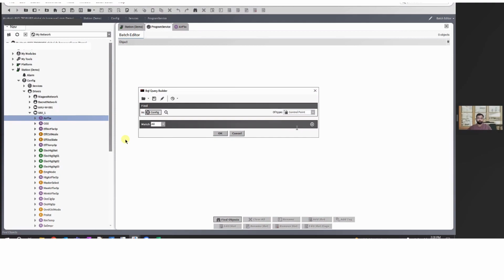In the find window, you can go to config since we're changing every point that has liters per second, to narrow it down to that. But what other options do we have? Let's say we only want to do it for the air handlers, or only for VAVs, or specific to one single VAV which has multiple temperature or airflow points. That's all done from the config window you see there.